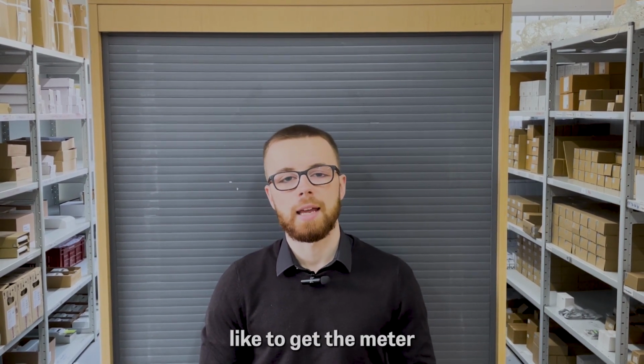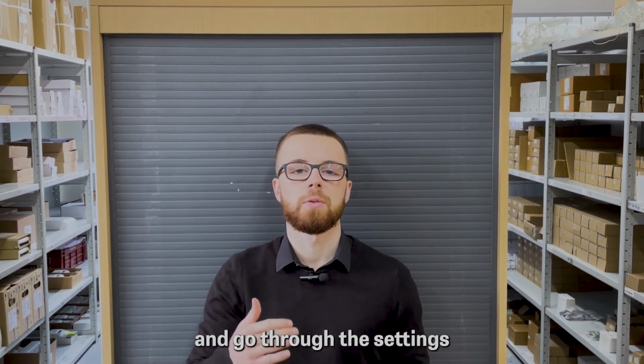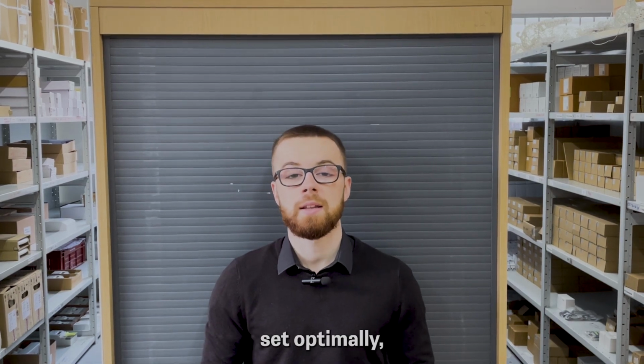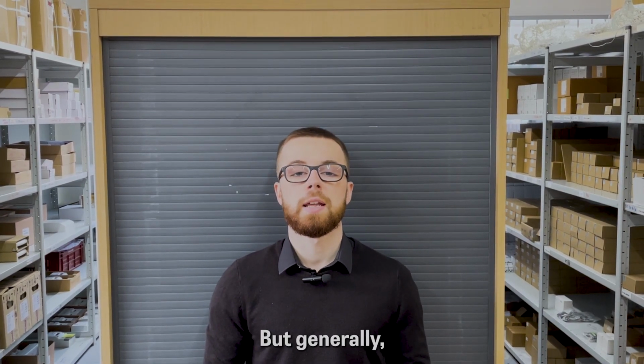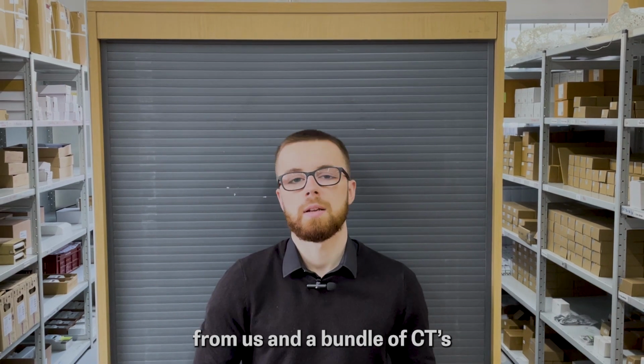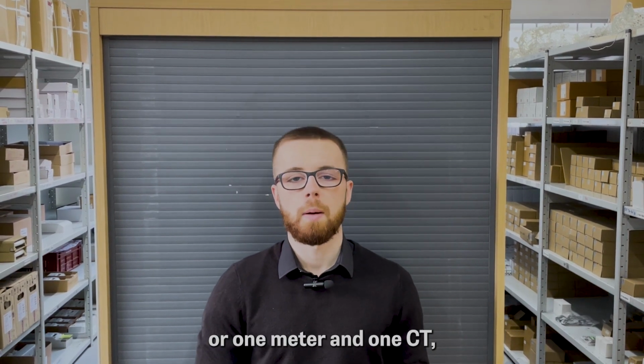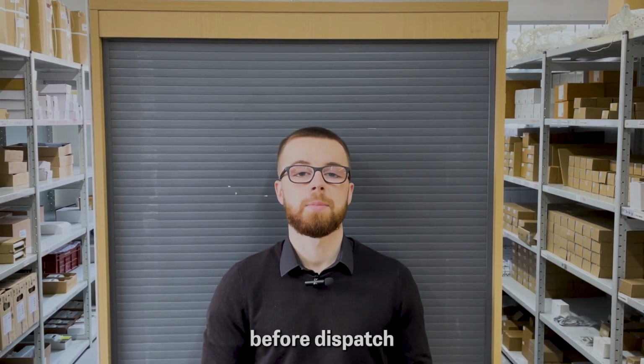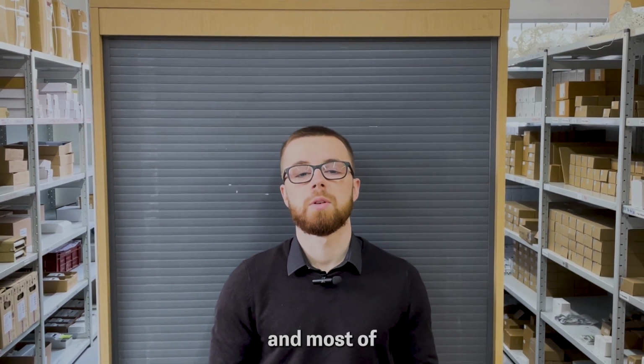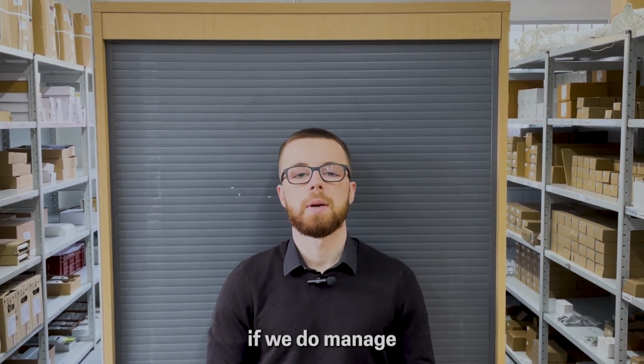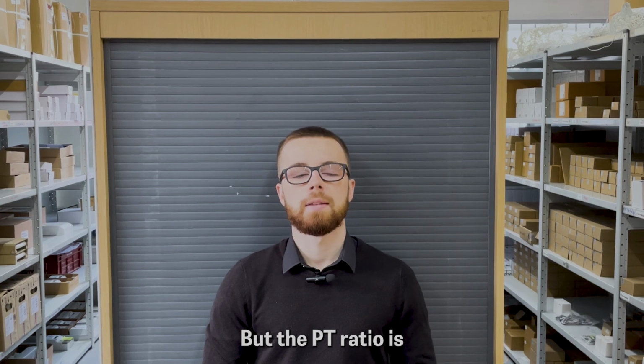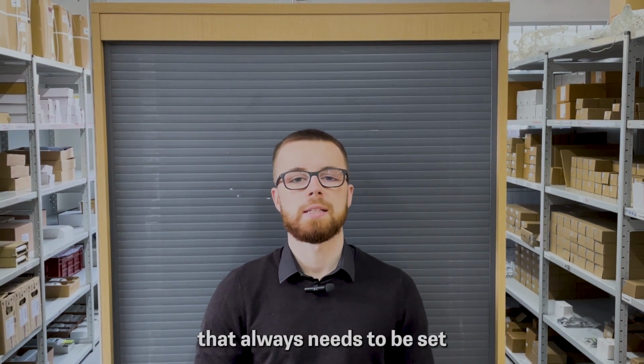A lot of people like to get the meter and configure it themselves and go through all the settings and make sure everything's set optimally, which is great. But generally, if you've purchased the meter from us, a bundle of CTs or, you know, one meter and one CT, we generally set it before dispatch. And most of the time we'll let you know as well if we do manage to speak to you. But the PT ratio is not something that always needs to be set.